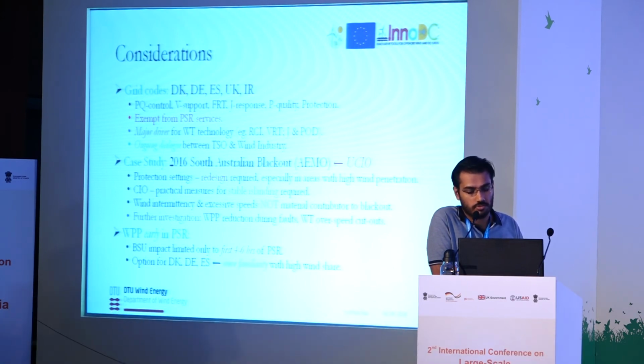One really nice case study that the Australian operator presented on the 2016 South Australian blackout in Cork at the WESC conference, the Wind Energy Science Conference, just this year in summer, was about how redesigning or just changing protection settings of the wind farm, especially in areas of high wind penetration, could have prevented unnecessary tripping of the large wind farm, and saved the system from splitting and leading to a blackout ultimately. And also, they do suggest more practical measures to be implemented for stable islanded operation. And they have done simulations that show that wind intermittency and excessive speeds are not really a material contributor to blackouts. But, however, further investigation is required because modeling the impact of wind on the power system resilience is quite a challenging task. And I mean, you can clearly see it took them maybe 2 years to get some sort of an initial study done.